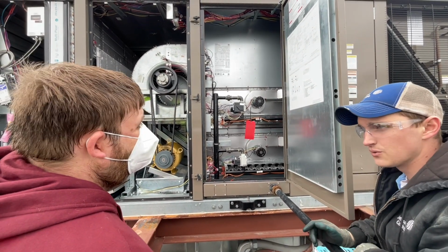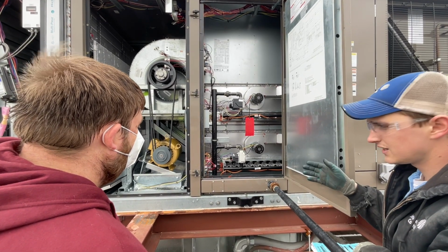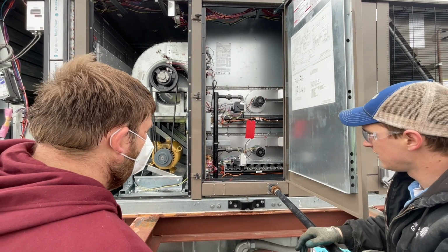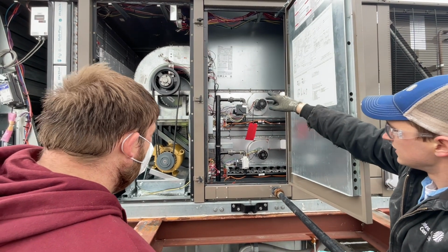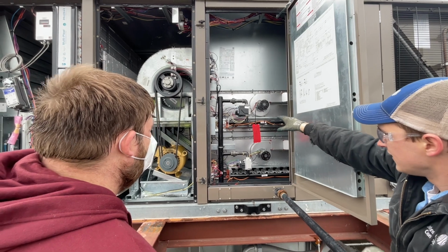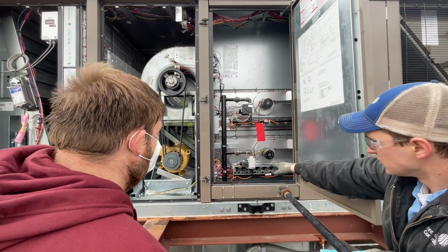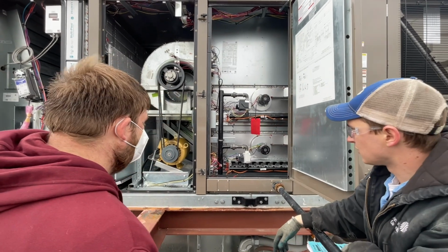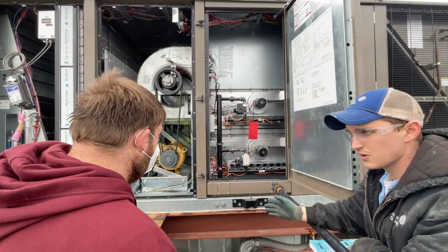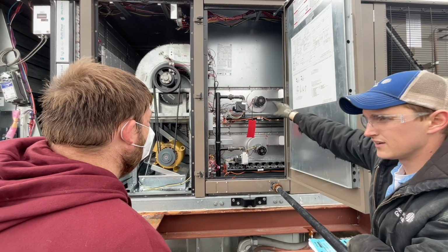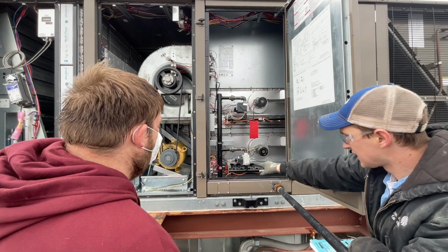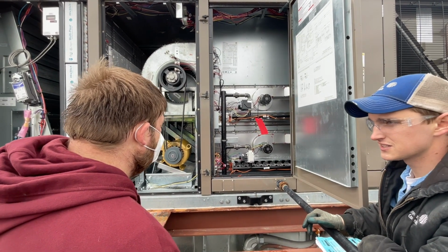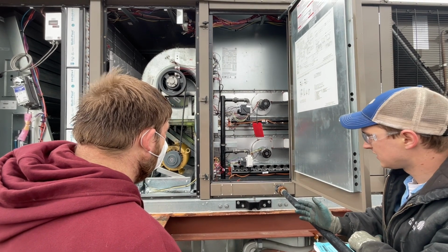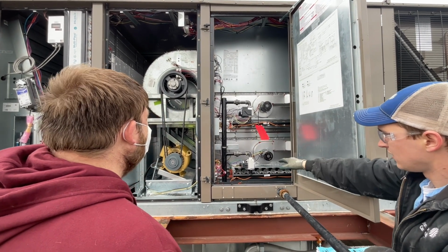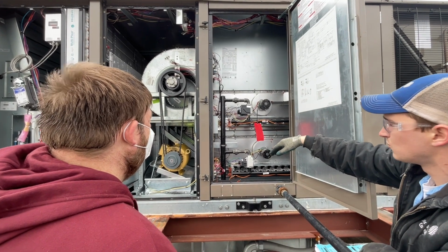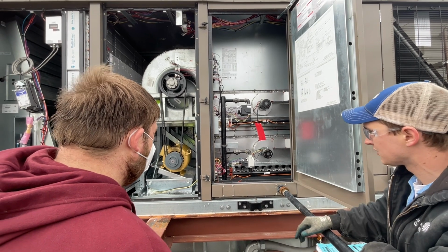First stage of heat is going to be 90-degree discharge air. Once it kicks up to second stage of heat, it's going to be 120-degree discharge air. That's going to send that information to these 2 boards, and then tell how much to modulate. Or this is a 2-stage gas valve. It will tell this gas valve what stage to be. So you could have it where you can see on the computer it's running 2 stages of heat. It'll only be running 1 of these, because it doesn't go by first stage, second stage. It goes by temperature for first stage and second. So that's a little bit different than most units like you might have seen. You could definitely have 1 running or 1 not running while it's calling for both stages. It's all dependent on temperature.